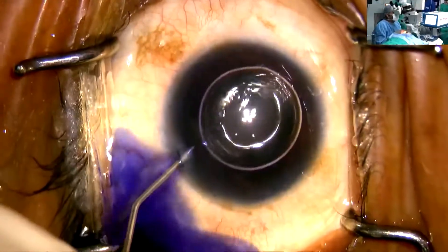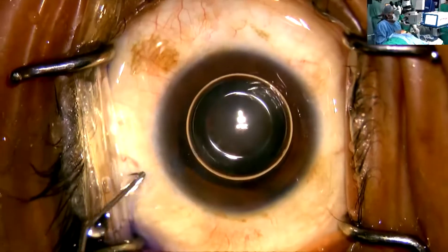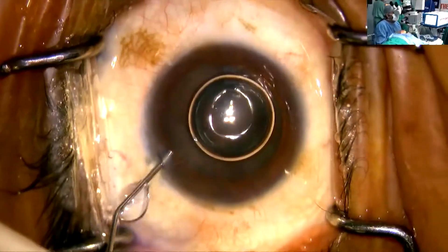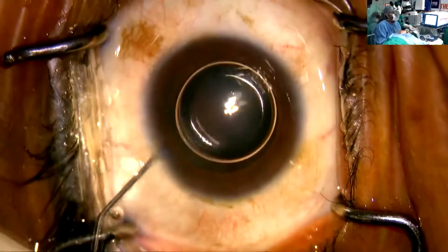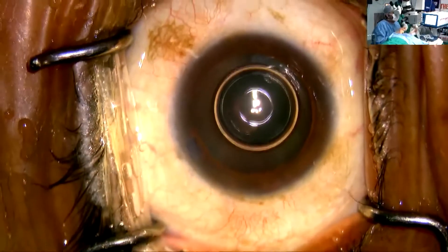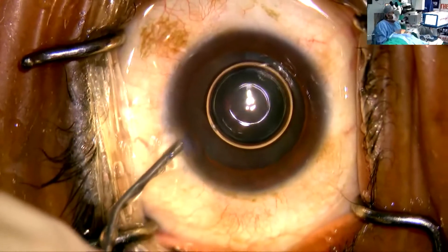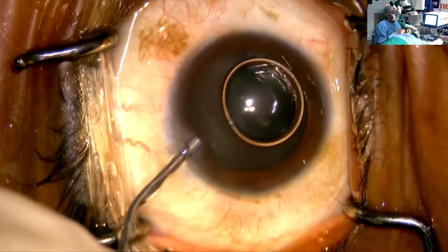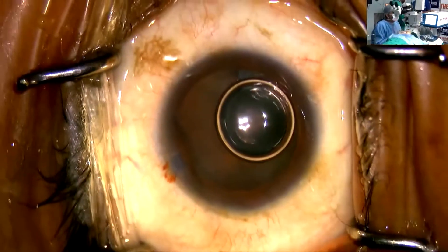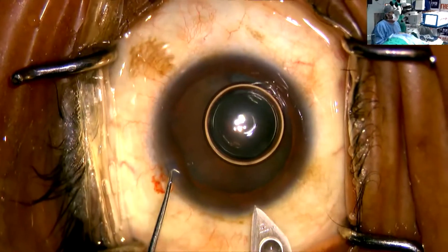The lens actually comes with a central bump and about four rings on the diffractive platform, coming up to a diameter of about 2.96 millimeters. Beyond 2.96 millimeters, the lens behaves like a true monofocal lens.